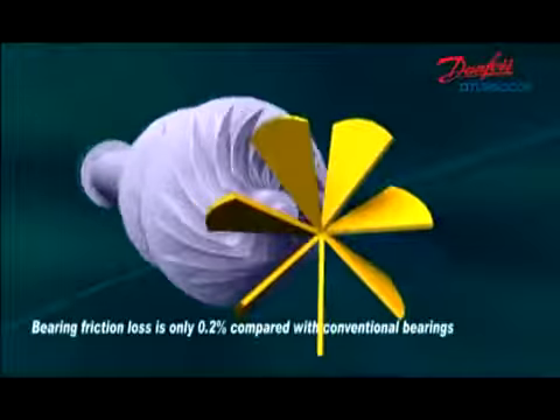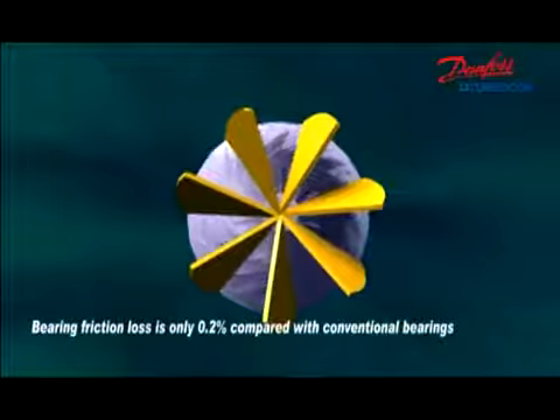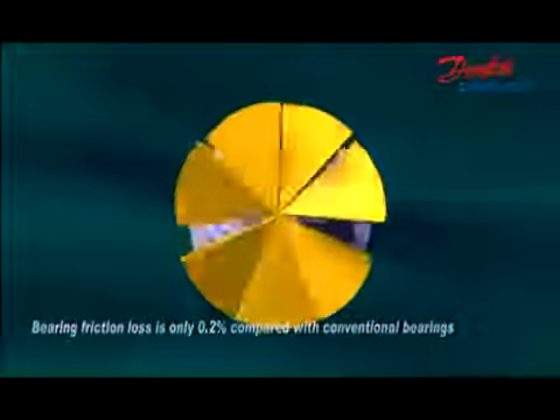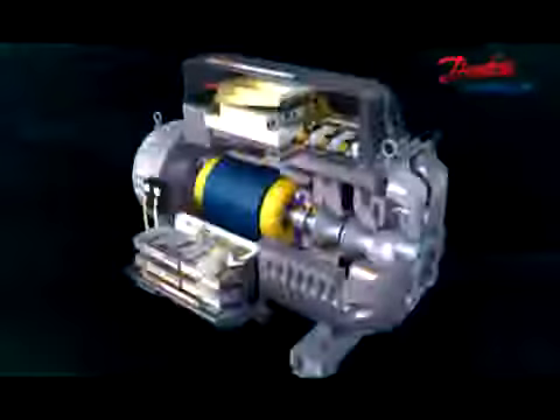Danfoss Turbocor is the first magnetic levitation bearing and variable speed driven centrifugal compressor in the world. It is composed of two-stage centrifugal compression, magnetic bearings, high-speed permanent magnet motor, compressor control, motor and bearing control, and condition monitoring. The rotor and impeller are the only moving parts, which ensures high reliability and high compression efficiency.